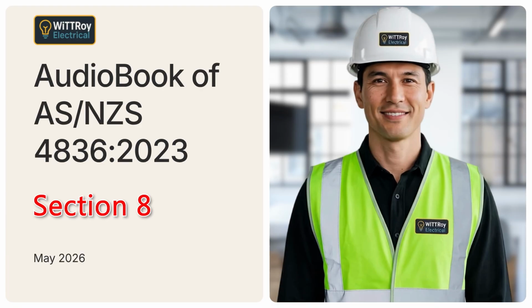In practical terms, do not assume a tool is electrically safe just because it has a plastic-looking handle. It must be the correct insulated type for the work. The insulation must also be in good condition. If the insulation is cut, cracked, worn, loose, melted, contaminated, damaged, or uncertain, the tool must not be used for electrical safety work. Insulated tools are part of the protection system, but they only work as protection when they are the right type and in the right condition.